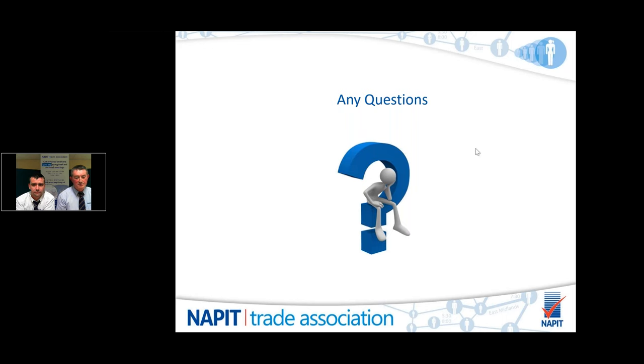Great, and we've just got time for a couple more questions. So Matthew's asking, if an installation has no RCDs present but is in a good condition, does it warrant a C1 or a C2 on an EICR? It really depends on where the socket is being used, to be quite honest. If the equipment could be used outdoors, it would have to go down as a C2. If, as stated previously, it was on a second floor, third floor, with no chance of equipment being used outside, it could go down as a C3.